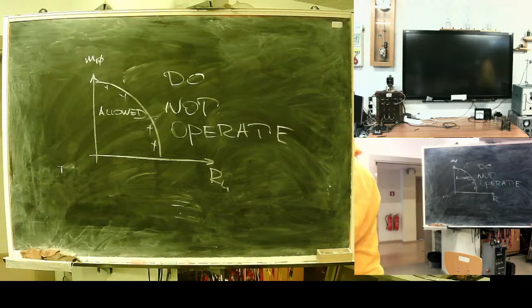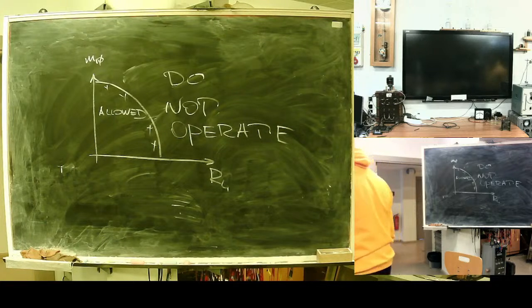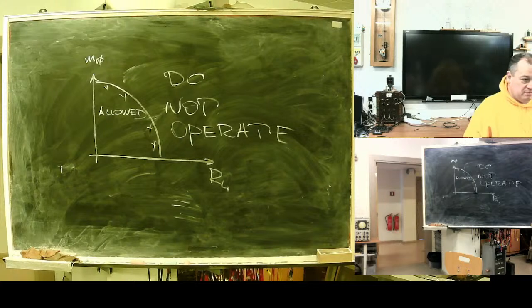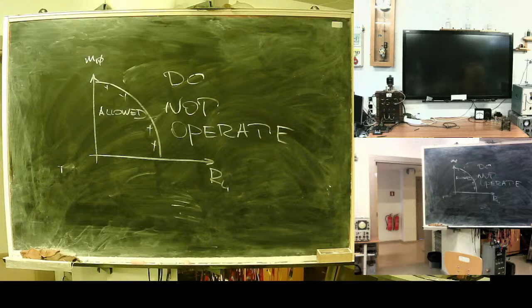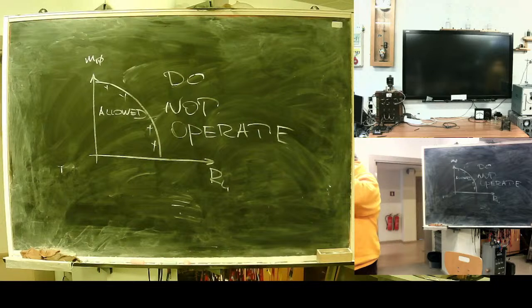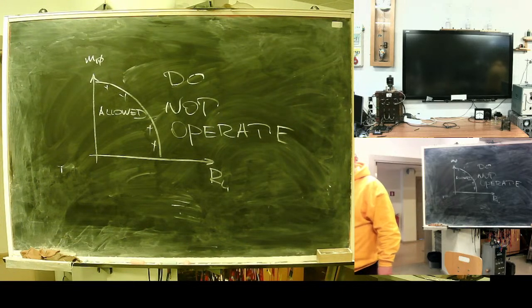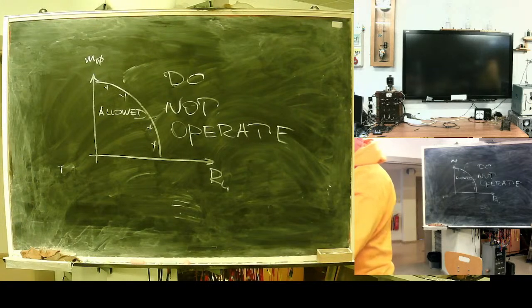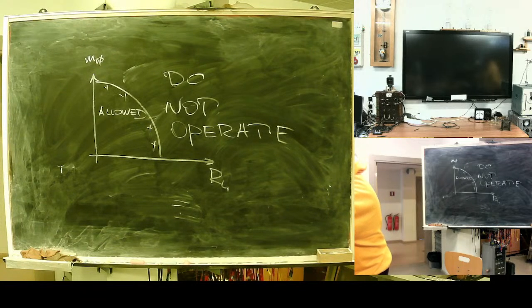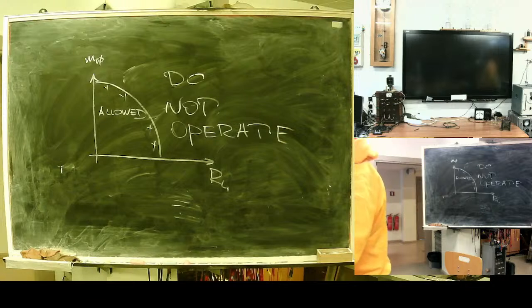This measurement core saturates at approximately 1.5 times rated current. Its overload capability is only 50%. It's thin. It's deliberately made to saturate because designers want to protect sensitive measurement, metering, and sensitive equipment from being damaged by overcurrents. This one should operate up to 40 times rated current. So if the rated current is 100 amps, this thing should operate up to 4,000 amps. That's why it's so massive, but it's not so precise. If you connect meters to this protection core, you'll be busted.